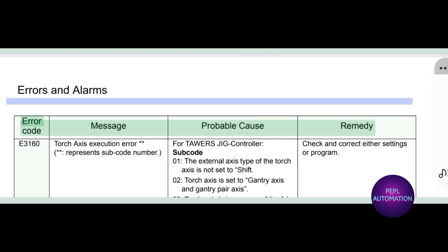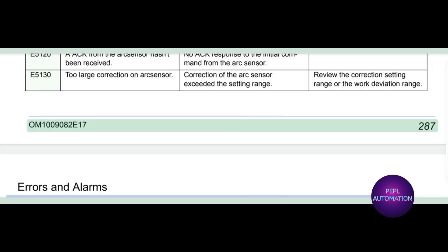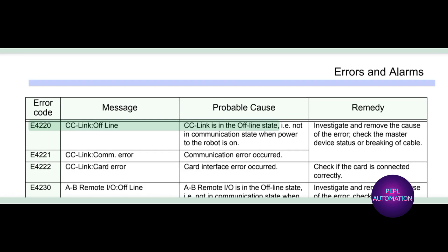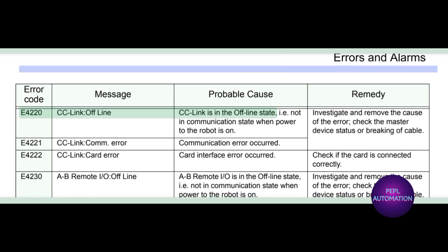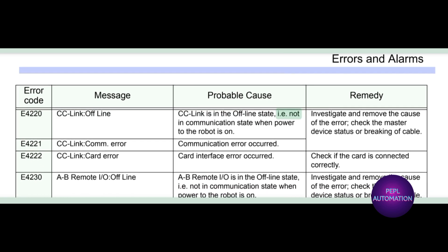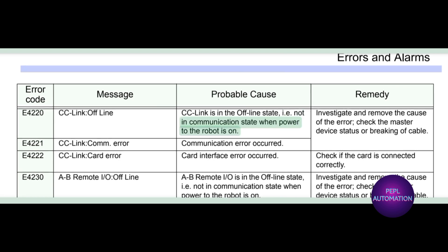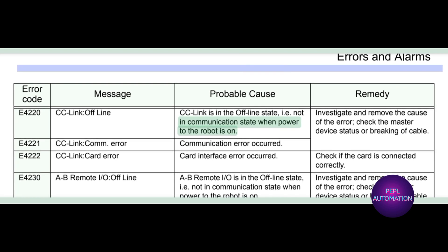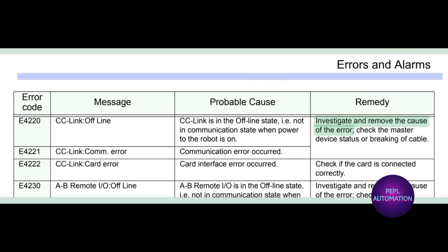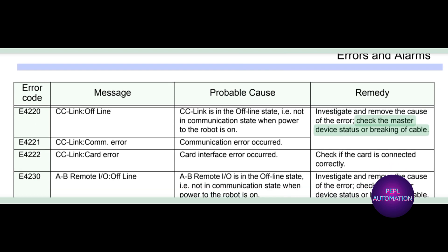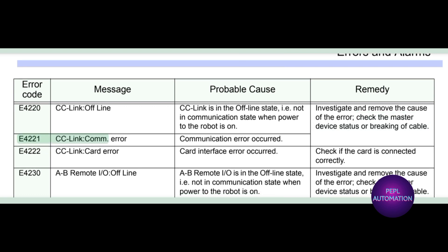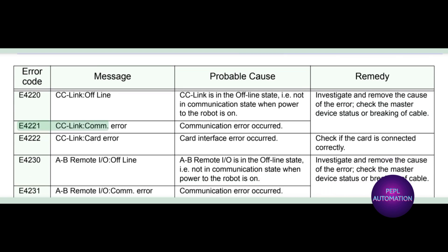E4220 CC link offline: CC link is in the offline state, i.e., not in communication state when power to the robot is on. Investigate and remove the cause of the error. Check the master device status or breaking of cable.